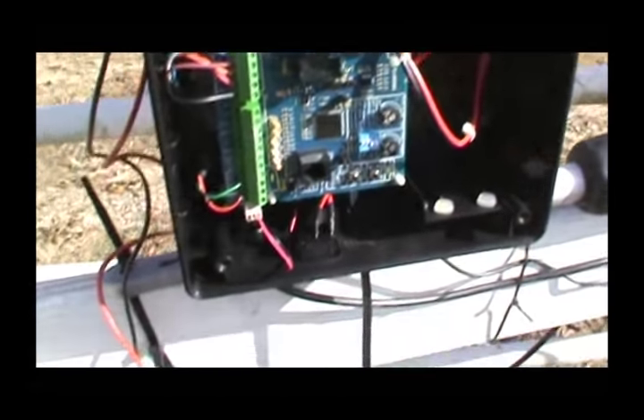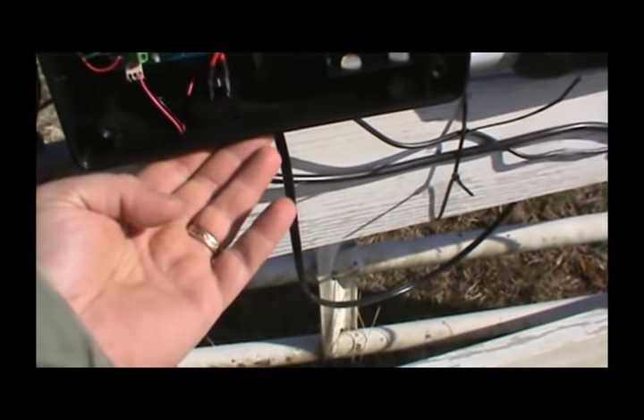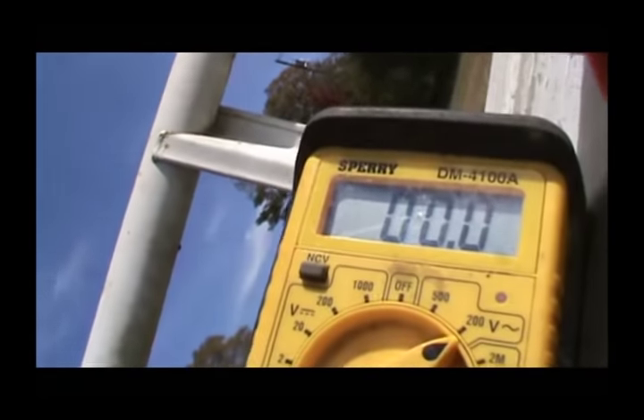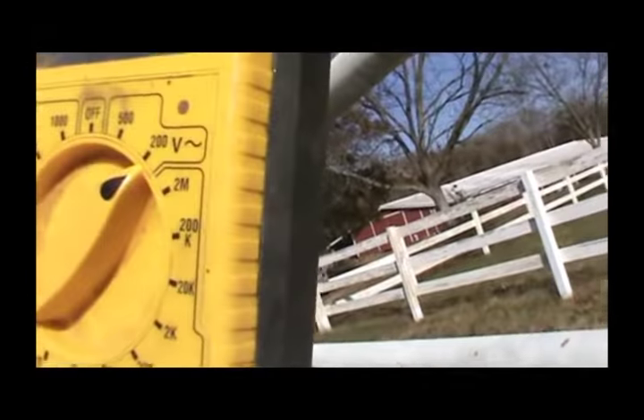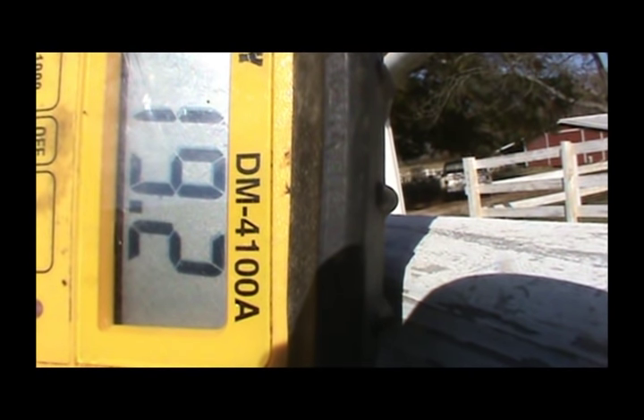But anyway, we're gonna go through our checks. I'm gonna go ahead and cut it back off because I got this arm just tied to this fence post, this fence right here. Anyway, I just checked the... it's gonna be hard to do one-handed, so what I'm gonna do is I'm gonna try to swap hands. It should have at least 18 volts AC coming in. You can see it right there, so this is AC. You can see we got 19.2.